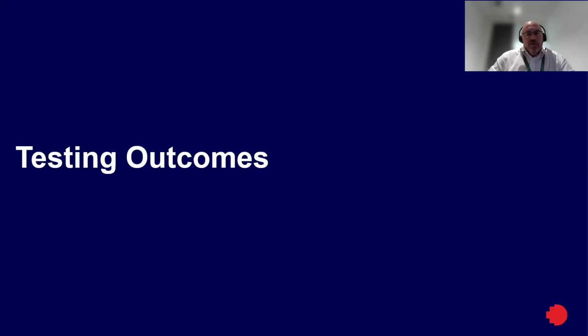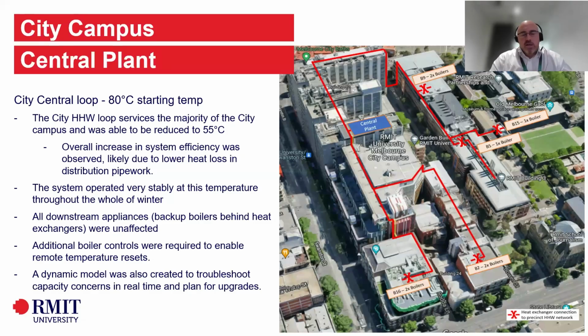So just to go through a few of the testing outcomes, the city plant, city central campus facility, that was an 80-degree starting temperature by design, and it had 20-degree temperature delta. We were able to turn that temperature down to about 55 degrees, and that was operated over the entirety of winter. The actual gas use, due to the lower losses through the extensive network of pipework, was also evident in the data as well. There was about a 10% reduction in gas use just associated with reducing that temperature. The system did operate very stably at this temperature throughout the whole of winter.